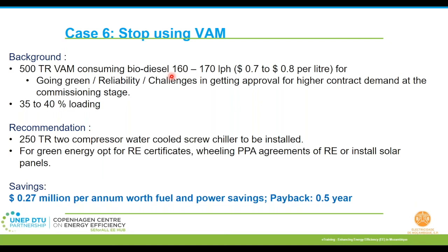When we measured, evaluated and compared, it's not just about the energy but also the economics. We saw that it is much cheaper for them to operate two 250 TR compressor based water cooled chillers rather than diesel fired VAM machines. Of course, as we have talked about, it's also about the efficiencies. Vapor compression machines are quite efficient in terms of energy conversion compared to VAM machines. Also, as I have mentioned, never use VAM machines when you do not have any waste heat sources available.